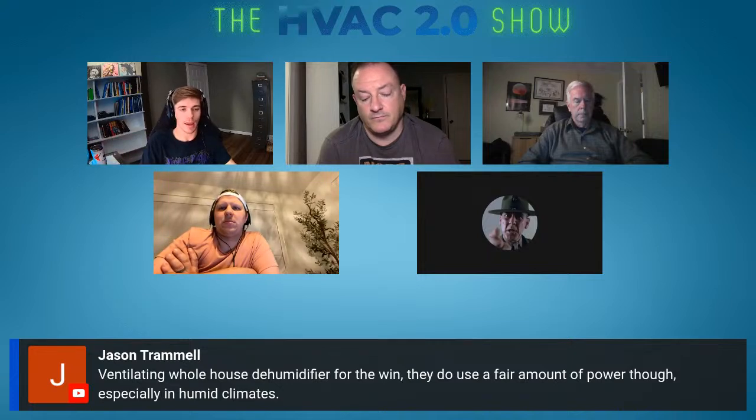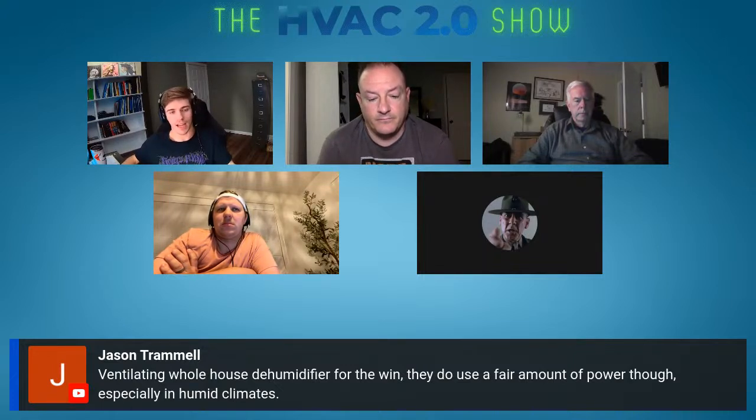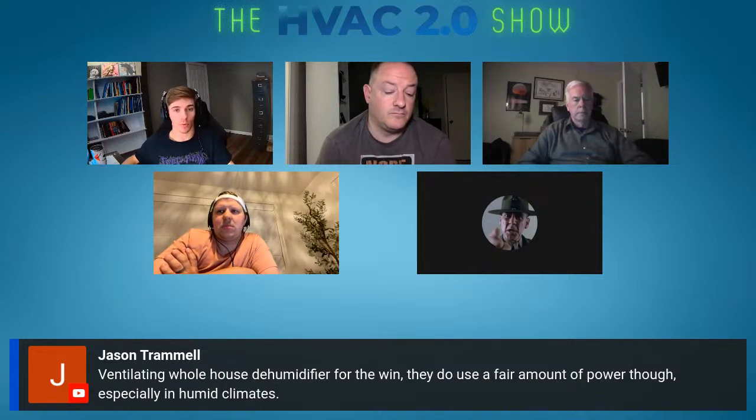So if you can avoid having to rely on a dehumidifier alone to handle that, such as going the ducted mini route, like the Mitsubishi, like the Midea and such, when you use those units, it pretty much dumps all of the responsibility onto the dehumidifier to maintain humidity, and it's just a very difficult job. So looking at routes of going, okay, we have to put in HVAC anyway, so what are the best HVAC choices to reduce that latent load as much as possible, so that way we don't have to rely on other means to control it.